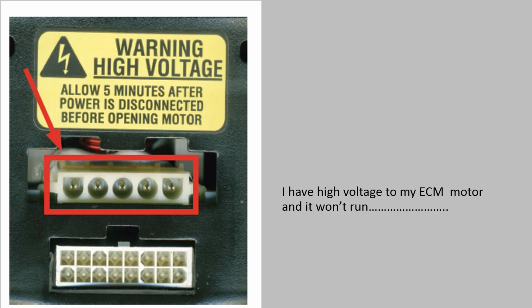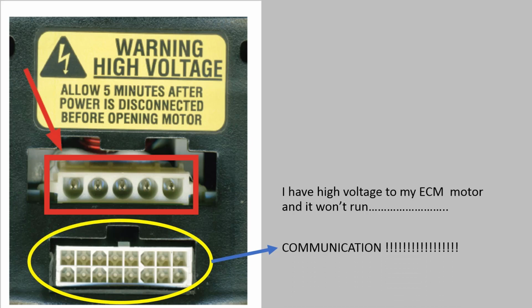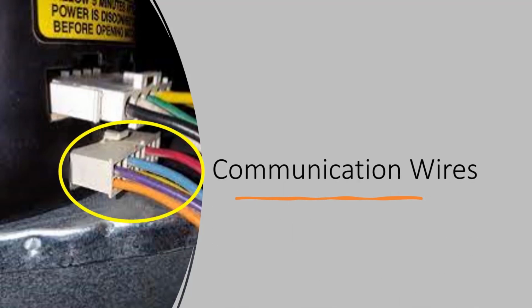One of the calls that we get a lot is from a technician who says, I have high voltage to my ECM motor, but it won't run. And our response is, what about your communication lines? The motor needs to be communicated to by the control board to tell it what it's supposed to do. Once you have verified that you have high voltage to the ECM motor, you next need to check the communication plug to make sure that you have communication from the control board to the motor. Without this communication, the motor does not know what it's supposed to do.